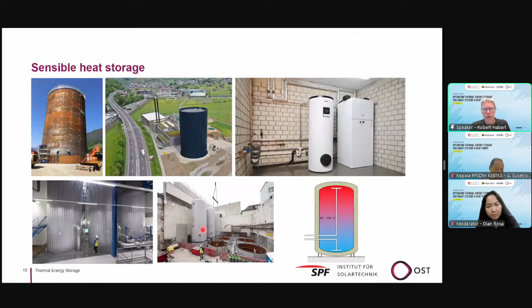But you can also use ice storages for use in solar ice systems. They make use of the high latent heat released during phase change. You see here a system with a heat pump that is providing heat for later use. And during that production of heat, it needs a source on the cold side, the source side of the heat pump. And you can use water as a source at a temperature of 0 degrees, where it releases a large amount of energy in the phase change. And that ice could be stored in an ice storage.